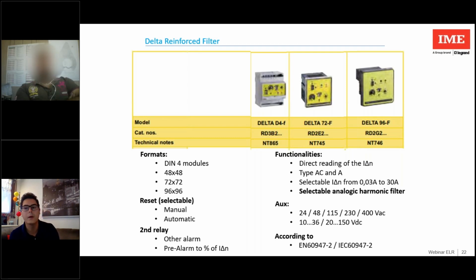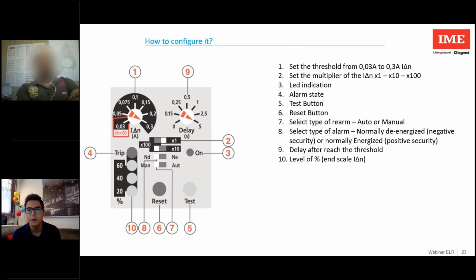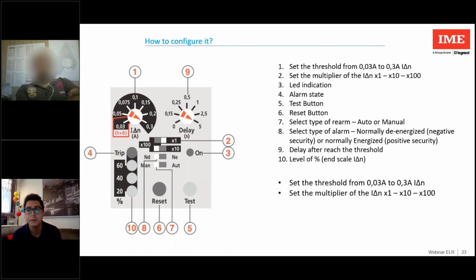Well, how can I configure this instrument? Very simple. On the left, there are the buttons and dip switches that you generally find on differentials. The layout changes a bit according to the format, but in general, they are all there. On the right, we find what everything means. What should I do? First, I have to set the intervention threshold from 0.03 to 0.3 amps. Second, I set the multiplier of this threshold, setting a value ranging from 30 milliamps to 30 amps.